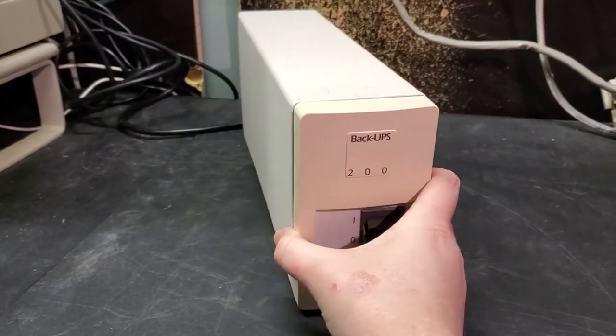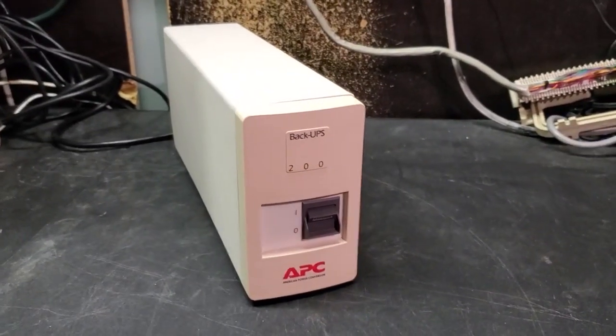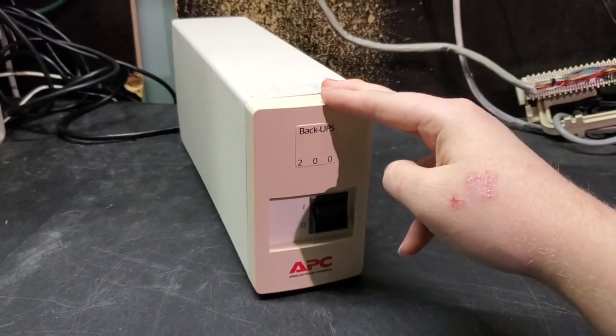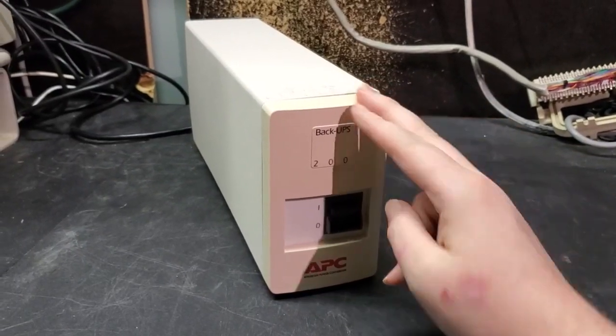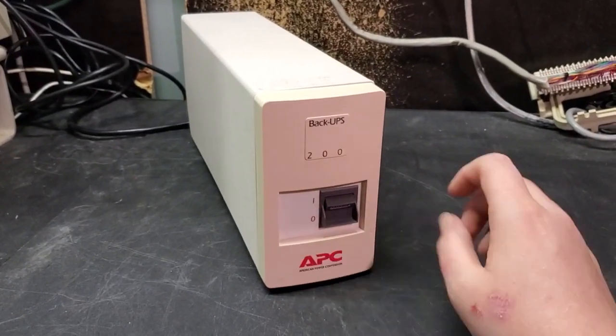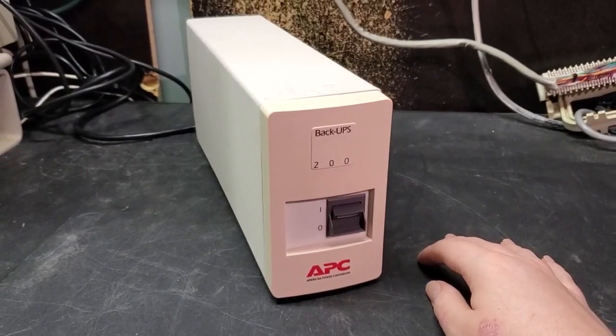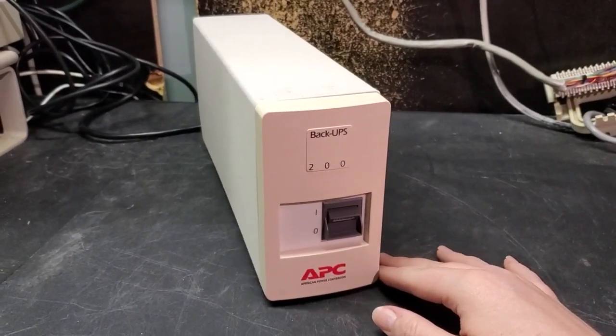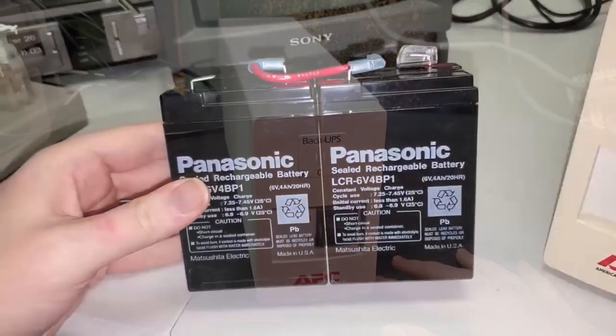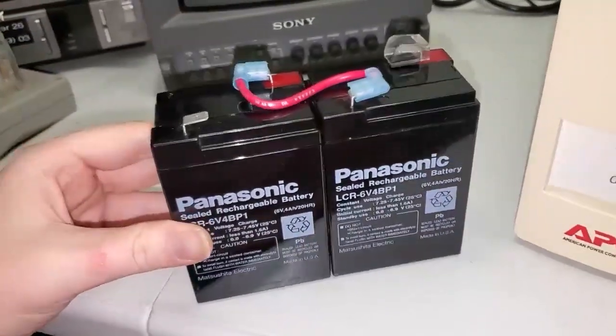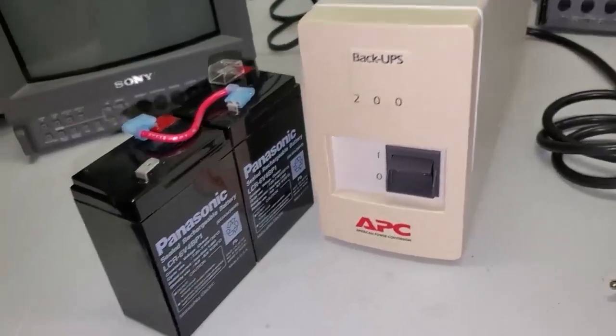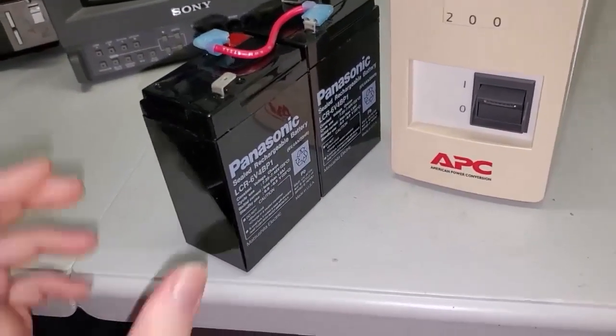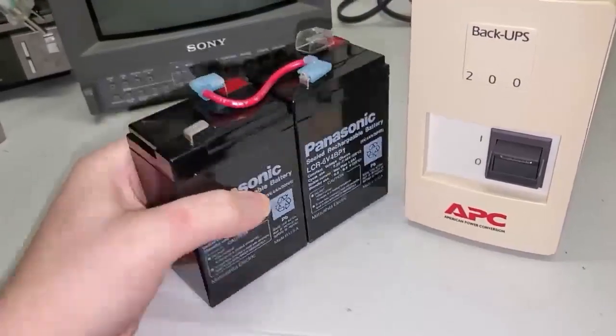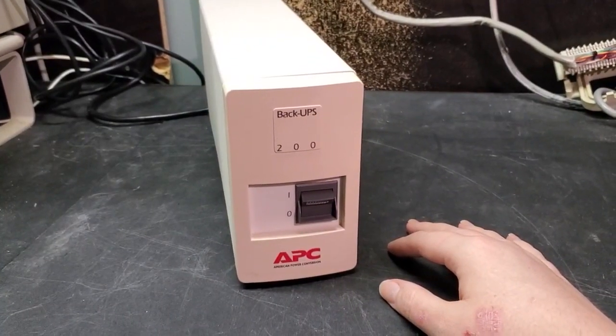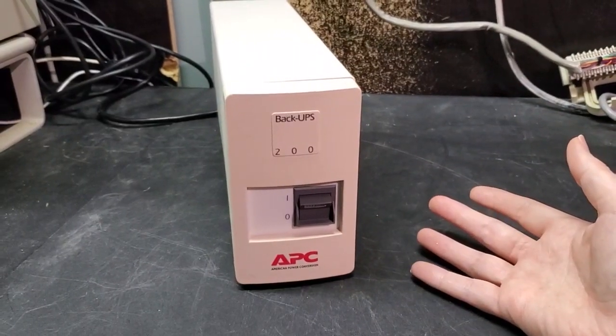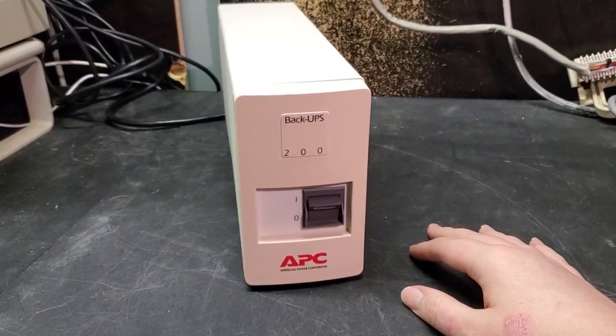The original battery that this takes is strange. This is a 12 volt system, which you might expect -- you know, APC's larger UPSs are 24 volts, so it's no surprise that a small one like this runs on 12 volts. But instead of a 12 volt battery, APC chose to use two 6 volt lead acid batteries in series, two 4 amp hour batteries in series. And that's strange. Why would they do that when there were perfectly reasonable 12 volt batteries that would be equivalent or maybe even slightly greater in capacity that they could have used?